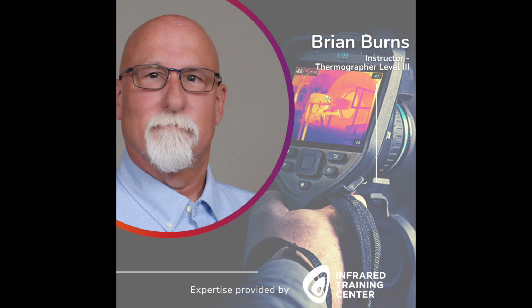There are different types, so look for loose panels. I've found a lot of loose panels on the roof, just by wiggling them. If it's loose, eventually it'll come off and can damage many other panels within the group. The other thing, as you can see on this array, is that you need to be thinking about your acquisition angle onto the actual panel. I'm going to discuss that in a little bit.